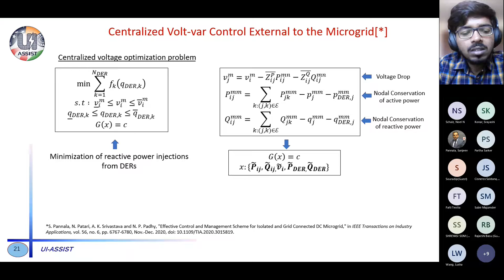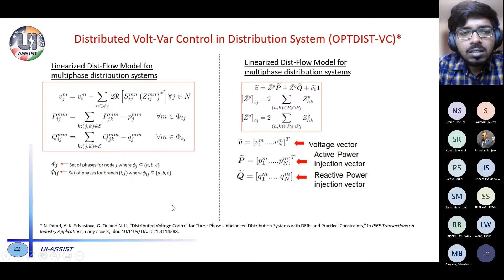Similarly, we have also done some work on distributed volt-var control on the utility side. Okay, yeah. What I mean by distributed voltage control is that in a distribution system, suppose there are a few microgrids, and each of these microgrids will only communicate among each other and then try to inject some reactive power to control voltage. So it involves linearized power flow equations. And this is the architecture. We have this distribution system, and we have some DERs, and these DERs will only talk with their neighbor DERs and send some information. So it will measure the local voltages, communicate only with the neighboring DERs, and then inject some reactive power in the next time instant.